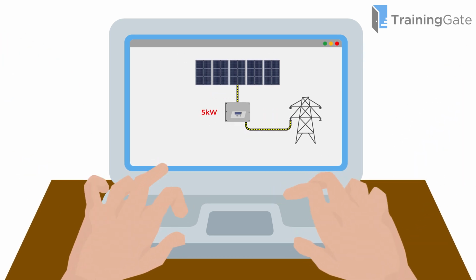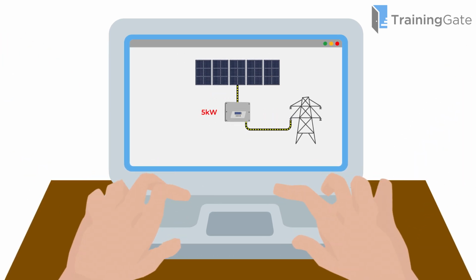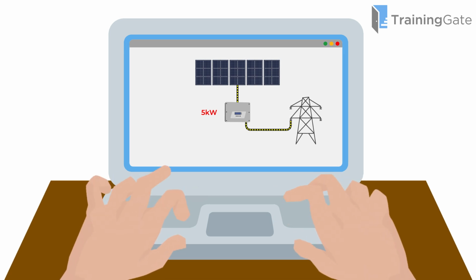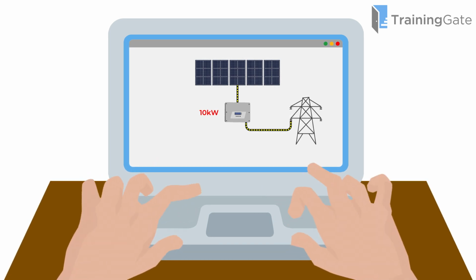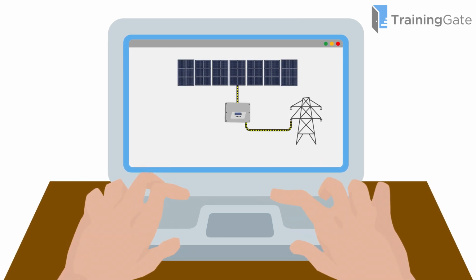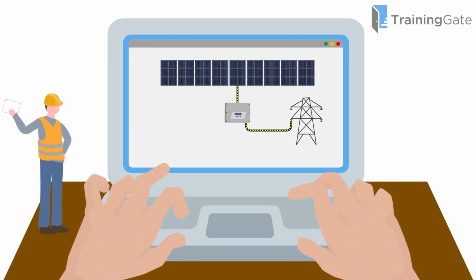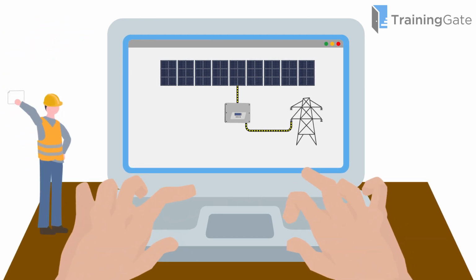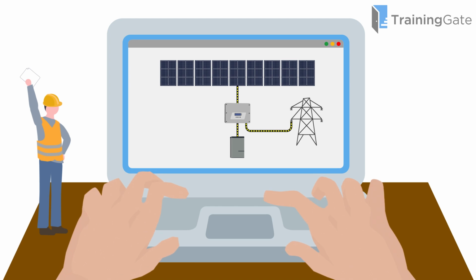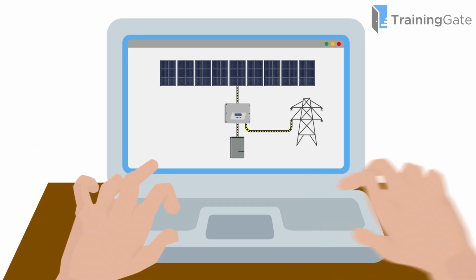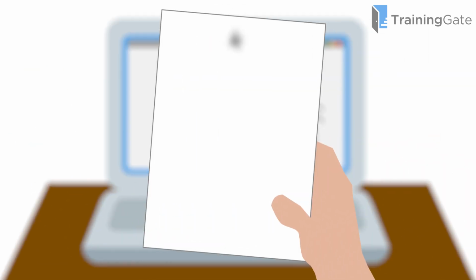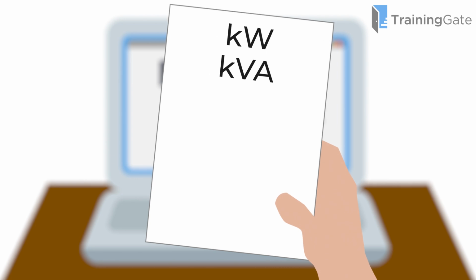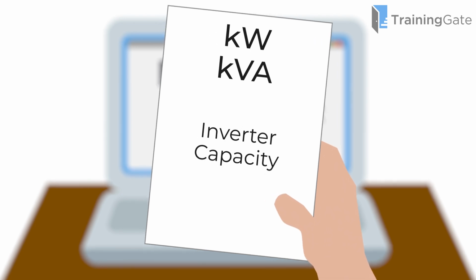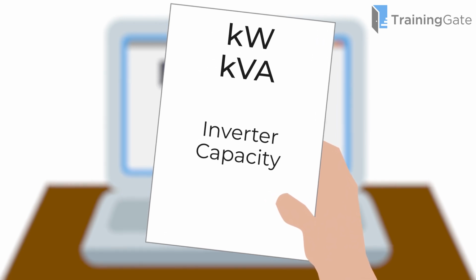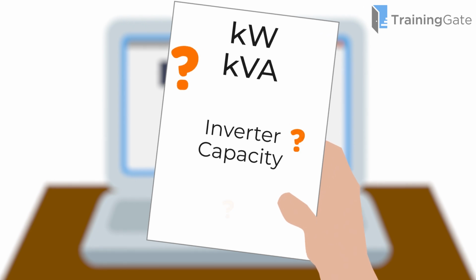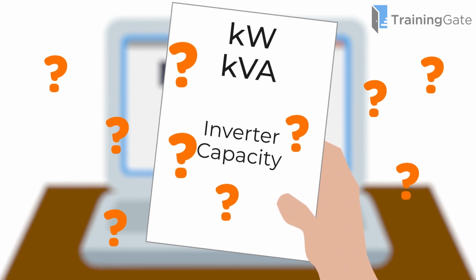Typically, 5 kilowatts is the upper limit for single-phase connections, although some networks allow up to 10 kilowatts. There are many variations. Some networks permit larger systems with special approval, and some include battery inverter capacity in the total allowable capacity. The limits can be set in kilowatts or kilovolt amperes, usually based on inverter capacity, but sometimes on the peak solar array capacity. When getting into specifics, it can become quite complex.